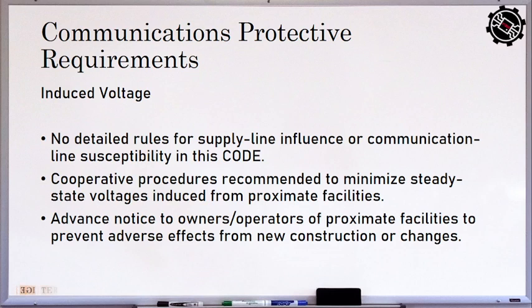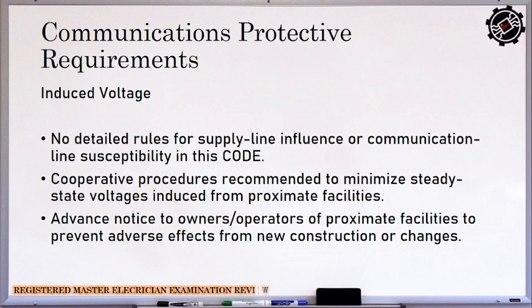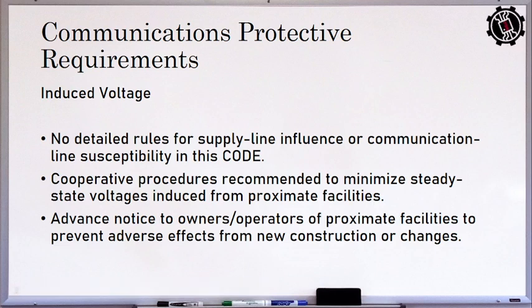For example, we have a system that passes along the sidewalk, and then there is a building along the sidewalk. The induced voltage may cause their entrance to become grounded, or customers may get a slight shock. So there must be advance notice to that facility that this can happen in case lightning strikes our line or there is a ground fault in our underground supply system. So there should be notice to the owners and businesses adjacent to our underground supply line.